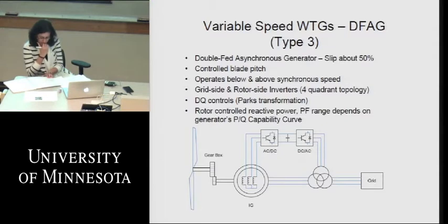We can independently control the direct and the quadrature axes. The direct axis most notably controls active power, or P, and the quadrature axis most notably controls Q, and so affects reactive power. And reactive power most effectively affects voltage. So if we can control D, we can control active power, which basically controls frequency. If we can control Q, we can control voltage because we can control reactive power.